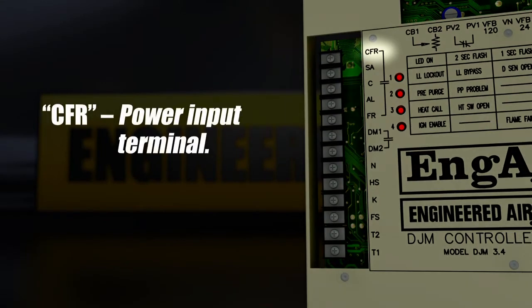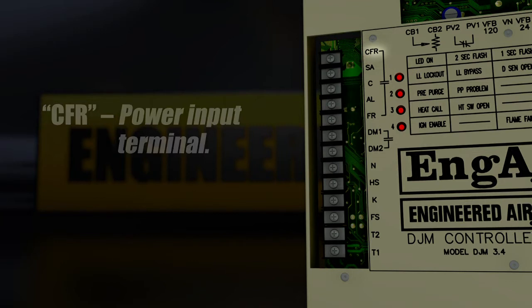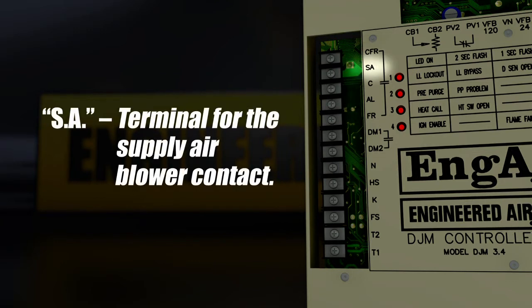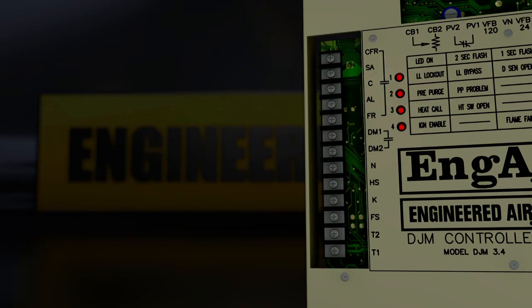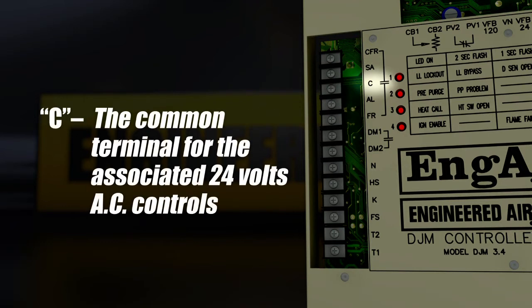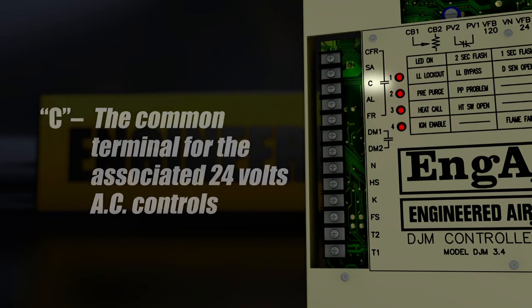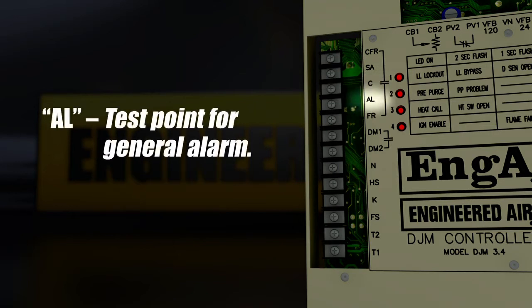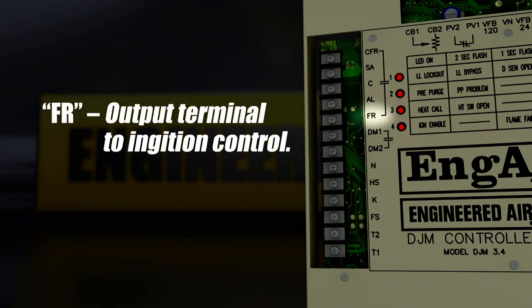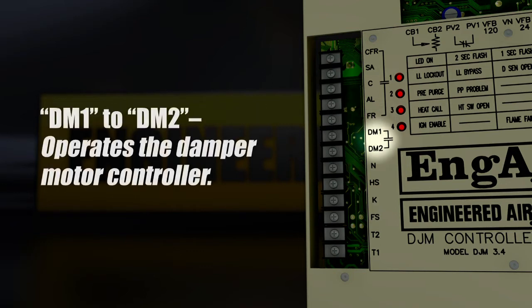The CFR terminal is the common power supply to control the flame relay. The SA terminal outputs power to the supply air fan contactor. C terminal is the common power supply feeding these two. The AL terminal is the alarm output relay contact. FR outputs to the flame relay. DM1 and DM2 close to enable the damper motor.